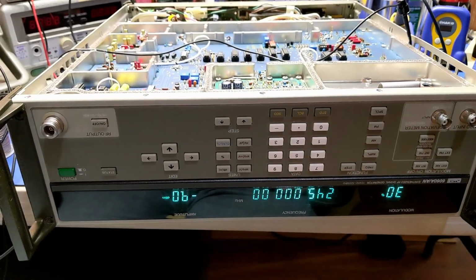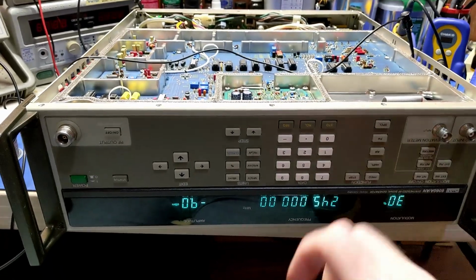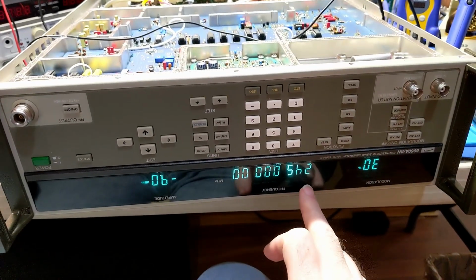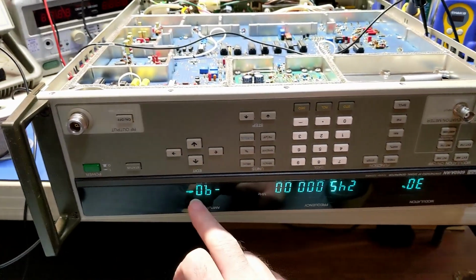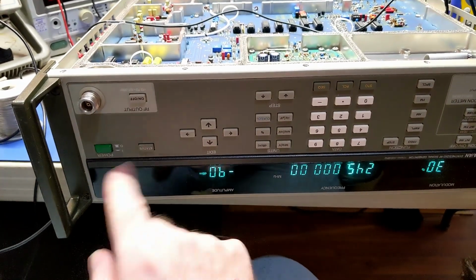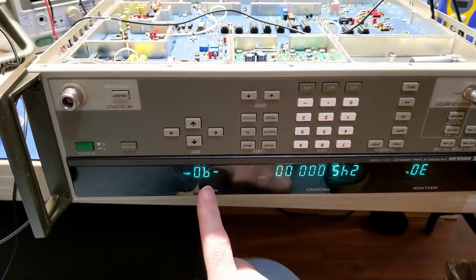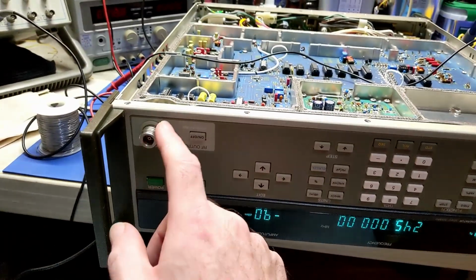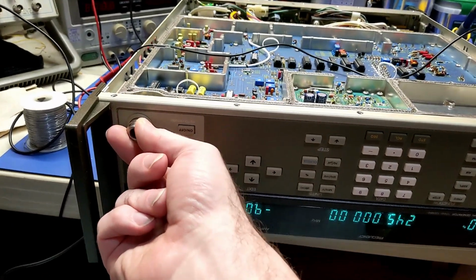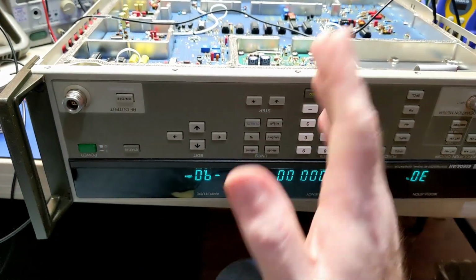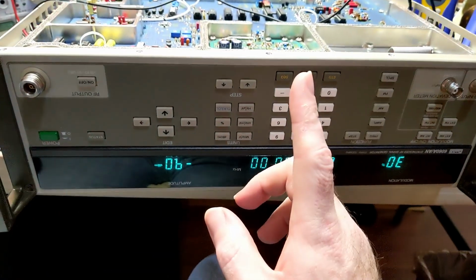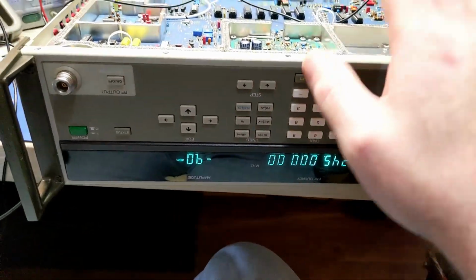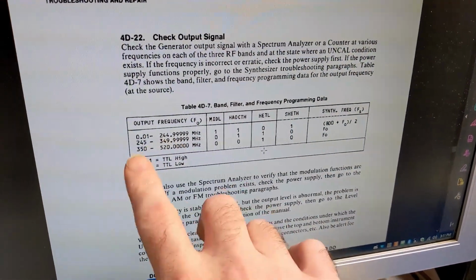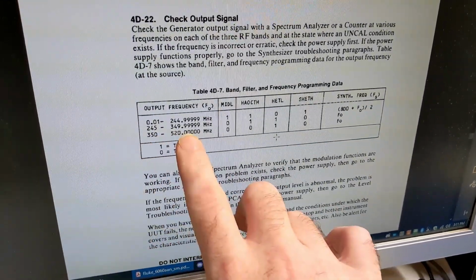Alright, I think I found our problem, or at least the general problem. Right now I'm at 245 megahertz at negative 9 dB and there's no faults. Now if I turn this up past 13 there is a fault. But I guarantee this thing has to be terminated at 50 ohms, and that might be why. So I'm going to ignore that for now, and if that's still a problem, we'll deal with that later. Right now, I want to work one problem at a time. And our problem is this machine has 3 bands. And here they are: band 1, band 2, and band 3.